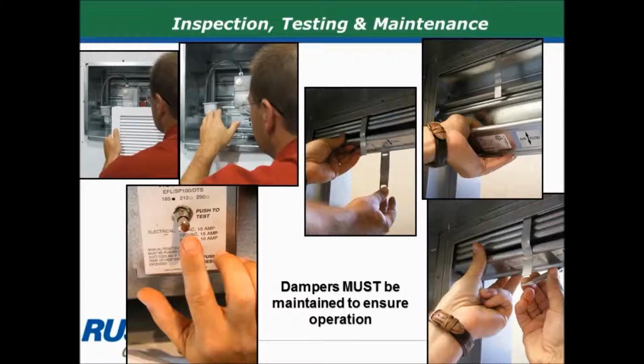On the right side of this slide is a typical curtain-type damper, and the mechanic at the facility is removing the fusible link and allowing the damper blades to close all the way, and then of course putting the blades back up in position and reapplying the link.